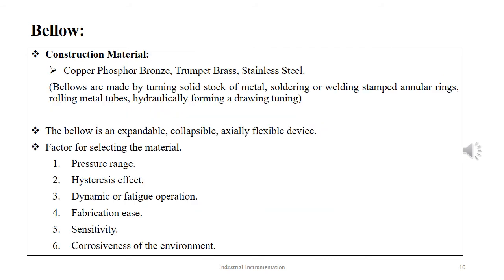The construction materials for a bellow are stainless steel, copper, phosphor bronze, or trumpet brass. The bellows can be configured as cascaded capsules. In industry, bellows are made by turning a solid stock of metal, by soldering or welding stamped annular rings, by rolling a tube, or by hydraulically forming a drawn tubing.